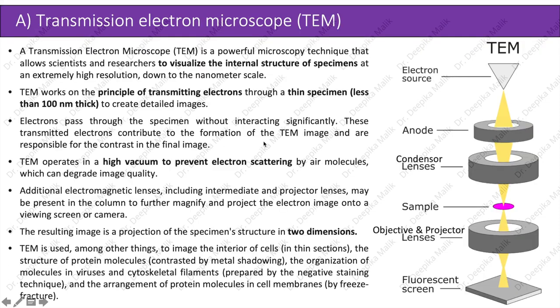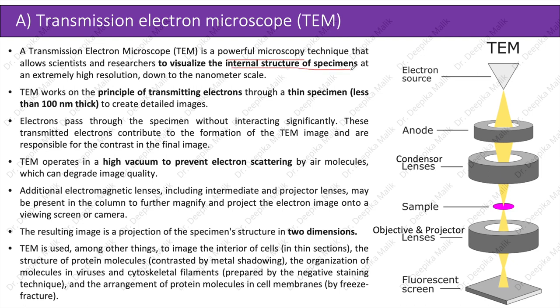Transmission electron microscope (TEM): a TEM is a powerful microscopy technique that allows scientists and researchers to visualize the internal structure of a specimen at an extremely high resolution, down to the nanometer scale. TEM works on the principle of transmitting electrons through a thin specimen less than 100 nanometers thick to create detailed images. Electrons pass through the specimen without interacting significantly, contributing to the formation of the TEM image and providing contrast. TEM operates in a high vacuum to prevent electron scattering by air molecules, which can degrade image quality.